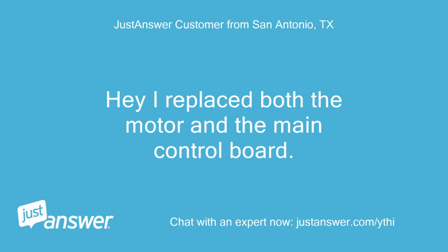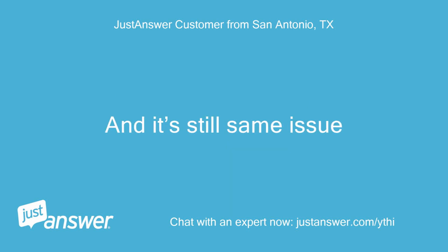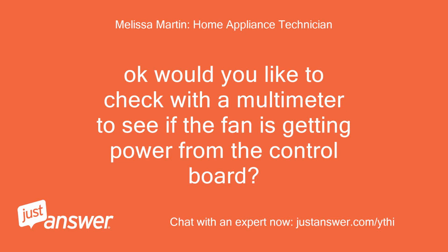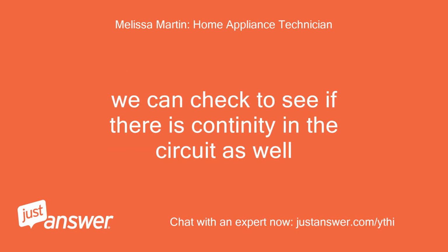I replaced both the motor and the main control board and it's still the same issue. Okay, would you like to check with a multimeter to see if the fan is getting power from the control board? We can also check to see if there is continuity in the circuit.